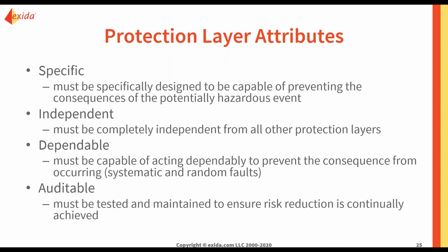And the other thing is that it should be independent, and that is very, very important because the concept of independence is not very clear across the board. When I do HAZOP and LOPA, independence means that it has to be completely independent from other protection layers, and also independent from the cause as well. For example, if the initiating event is a flow valve failure, but the alarm that you're going to use is related to the controller that's controlling the flow valve, then that is not an independent IPL.